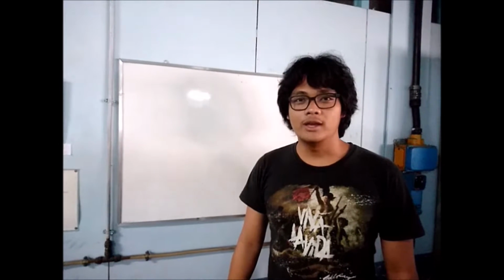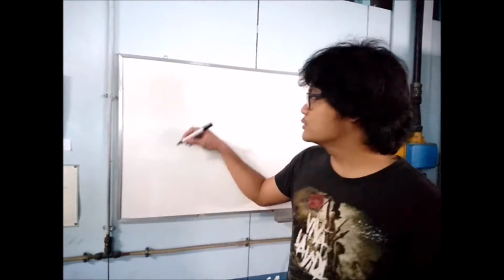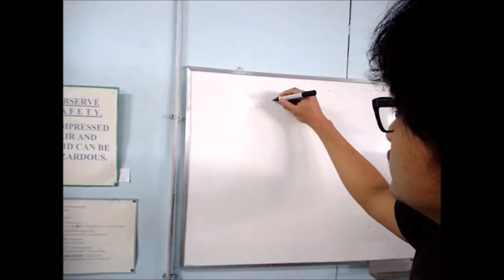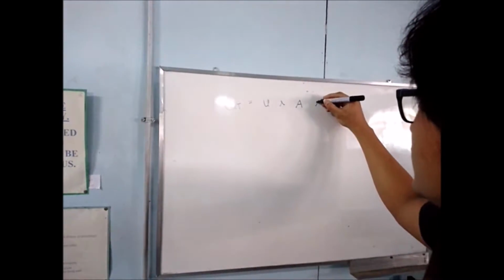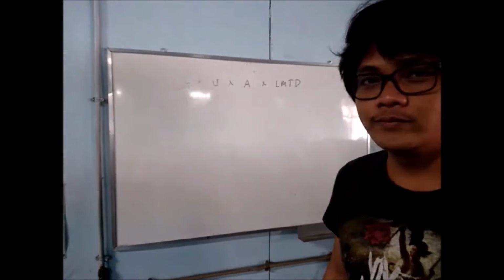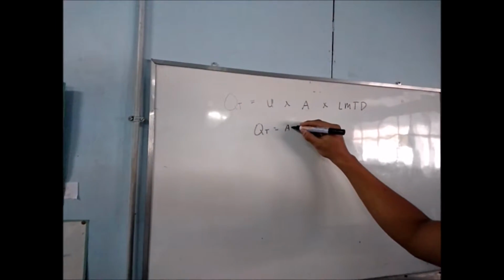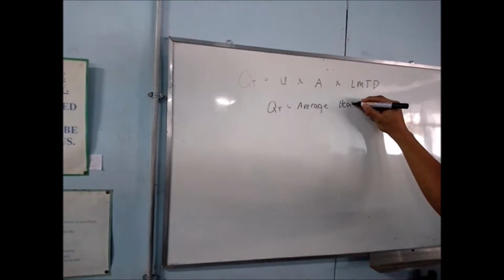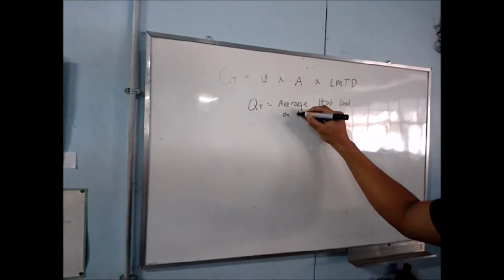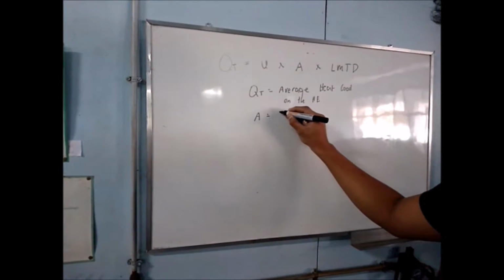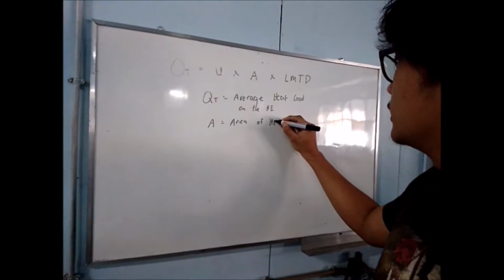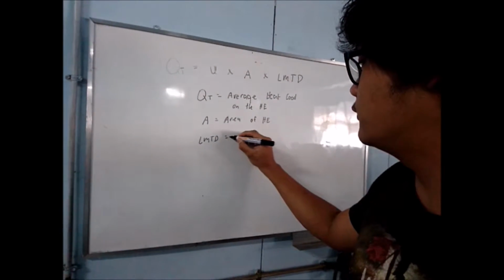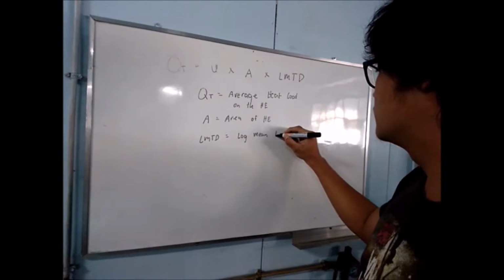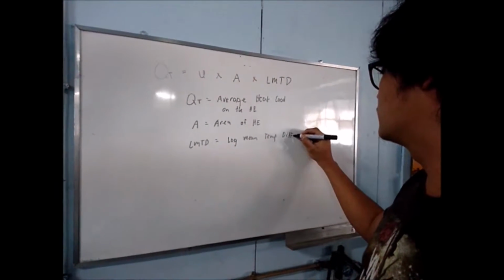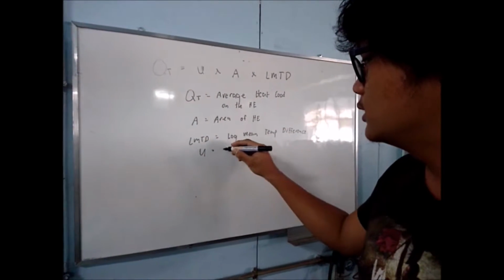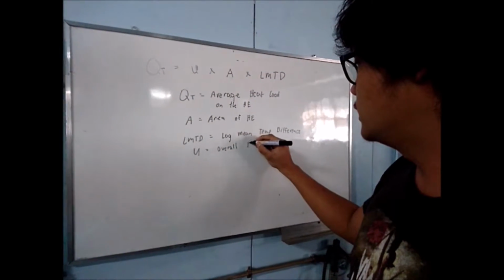In order to compute the overall heat transfer coefficient in the heat exchanger system, we have to use the formula Qt equals U times A times LMTD. Where Qt is the average heat load on the heat exchanger, A is the area of the heat exchanger, LMTD is the log mean temperature difference, and U is the overall heat transfer coefficient.